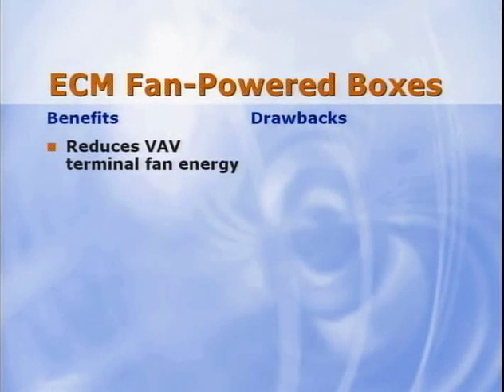Parallel fan-powered VAV boxes can save energy because they use warm air from the ceiling as the first stage of heating. This delays the need to use new energy by activating the heating coil. The use of electrically commutated motors, or ECMs, in fan-powered VAV boxes has become increasingly popular due to several benefits. The first is energy savings. An ECM is a brushless DC motor that's more efficient than the single-speed, fractional horsepower motor technologies that have traditionally been used in fan-powered boxes.